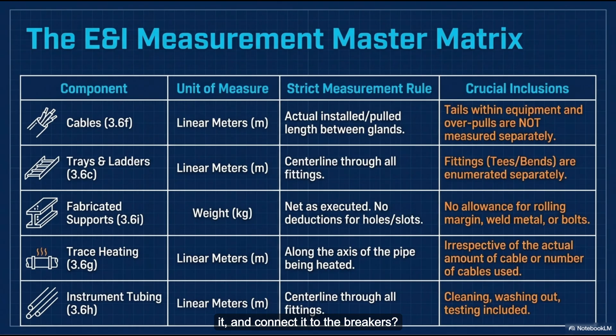The preambles strictly state that the cost of tails within the equipment, and any overpulled length or waste, must be included in the contractor's base rate for the installed net length. They literally have to buy wire they know they will never get paid for directly, and then try to hide that cost inside the per meter rate of the wire they do get paid for. It forces a brutal level of precision on the estimators. The client is basically saying, I only want to pay for the literal distance between these two boxes. It is your job to predict how much extra tail your electricians will need, how much waste you'll generate from cutting, and bake that into your bid.